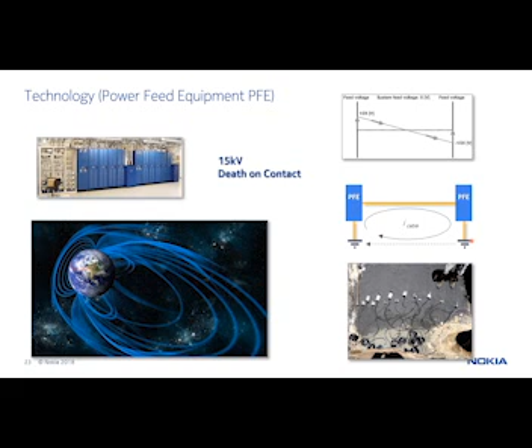This is what an ocean ground looks like at the beach. They'll basically have these anodes, all connected together, and they put in what's sometimes just called coke—it's like a graphite type material that's conductive. You can see here it's like a phosphorus type volcanic beach soil. So they're trying to get a good ground connection from the power feed to the earth itself.